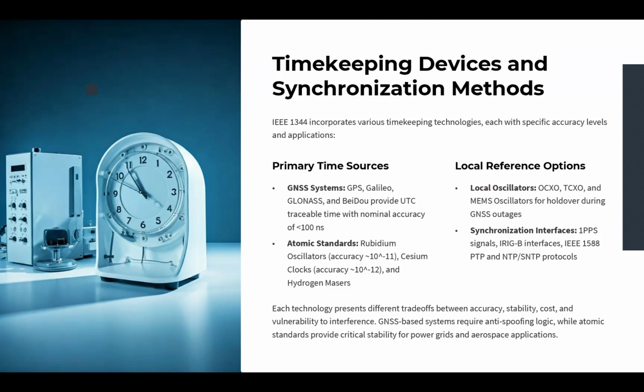Now, another type of local reference is the synchronization interfaces. This type supports a wide variety of hardware and network interfaces. It could be one pulse per second clocks, or IRIG interfaces, or the IEEE 1588 PTP protocol or the NTP protocol. IEEE 1344 allows the combination of these methods, provided the time quality metadata and alarm handling are there. We should implement all of them correctly.